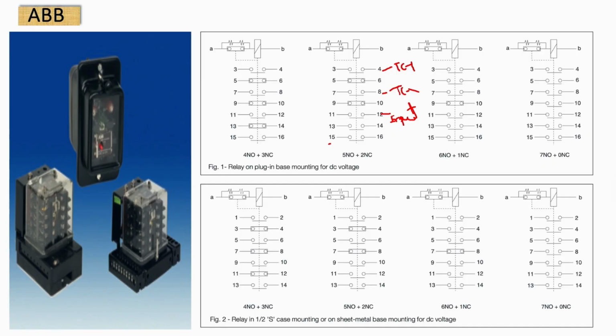Okay? If you need to do any interlocking, you can use this. If you need to do any NC, that means CB locking. Okay? You have to interlock the CB breaker so that when the master trip operates, my breaker should not close. So for that also you can use these NC contacts so that as soon as the master trip operates, this 9, 10 becomes NO, then my breaker will not close.